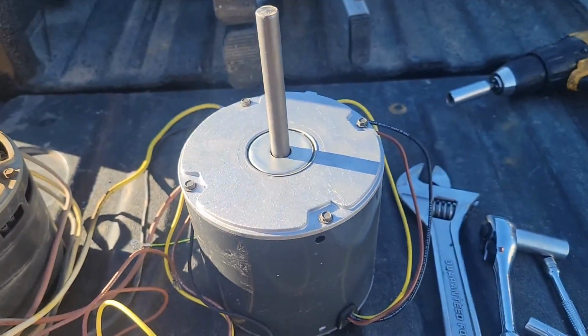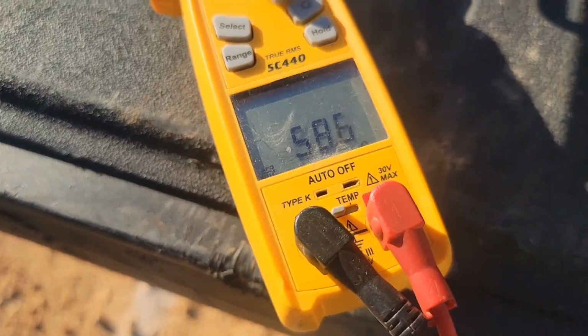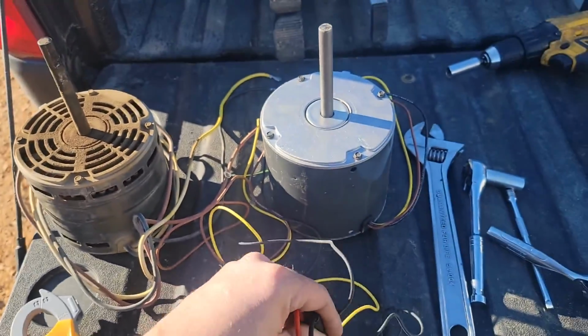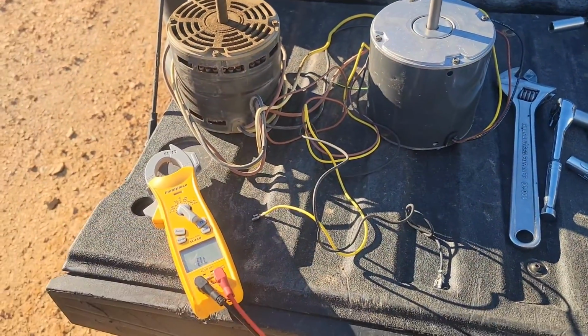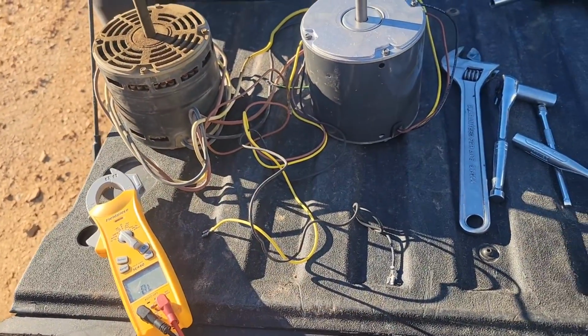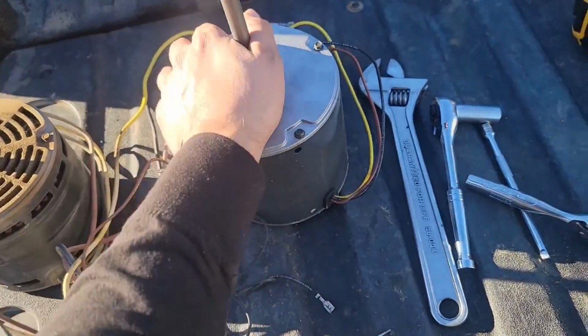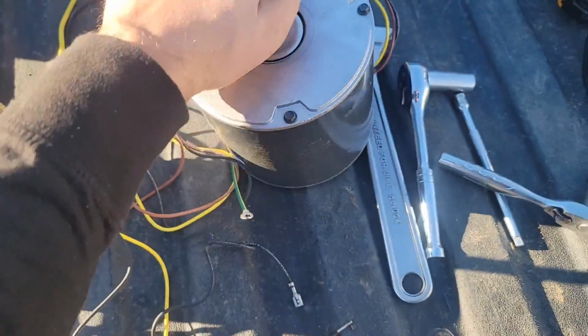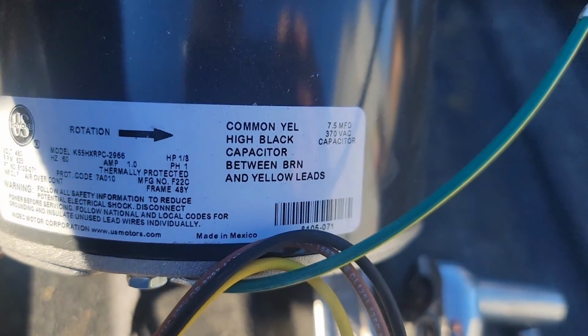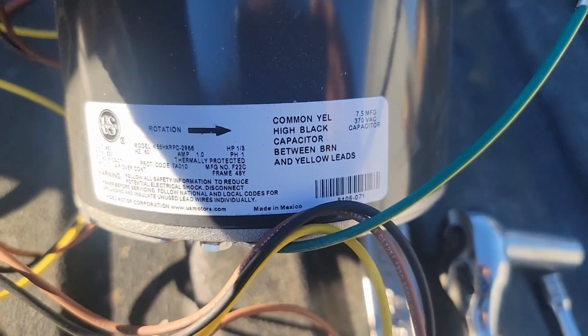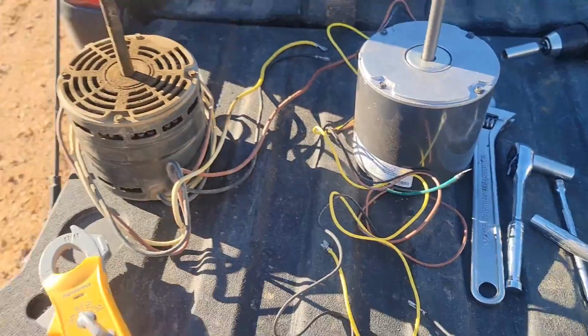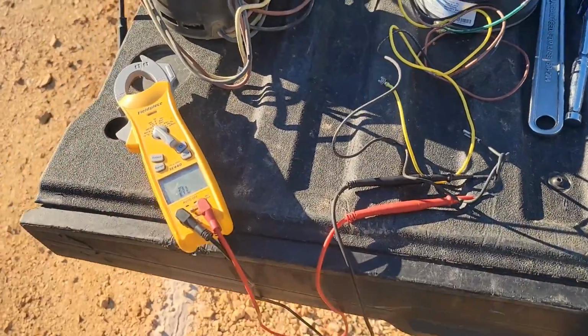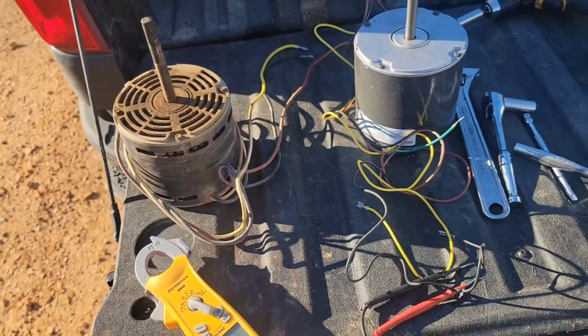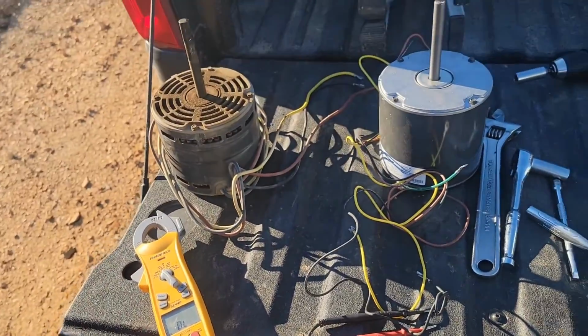Now I'm going to measure the new motor. All right, checking the resistance between the black and the yellow on the new motor. 58. So there is a little bit of a resistance difference between the two motors and the yellow and the black wire. Interesting. Excited to see what happens when I put this motor in. And as you can see, the yellow was common, the black was high, and that's what we were measuring. All right, we just measured the resistance of the windings. Now let's put the new motor in.